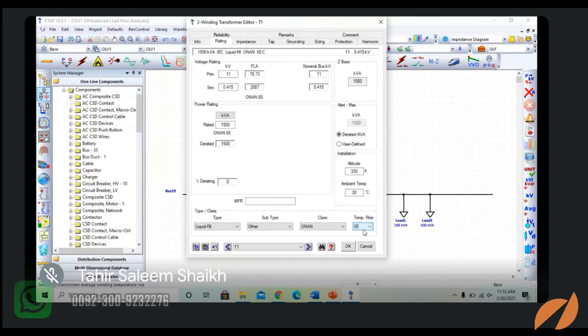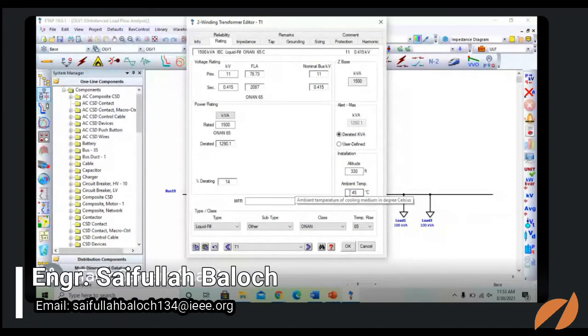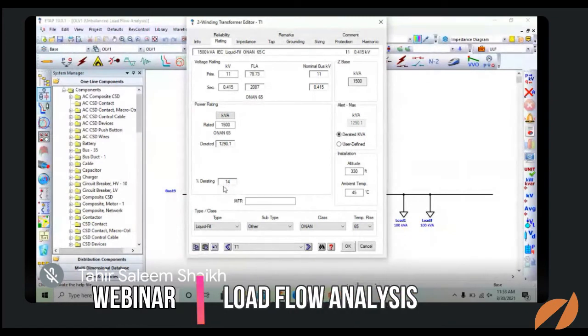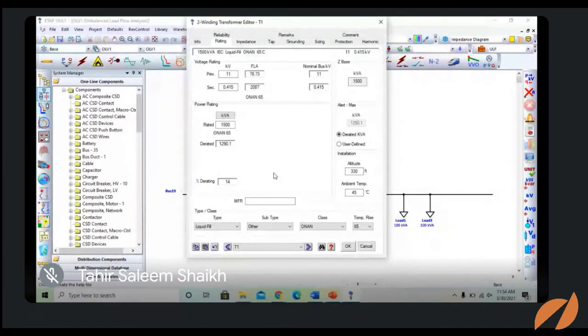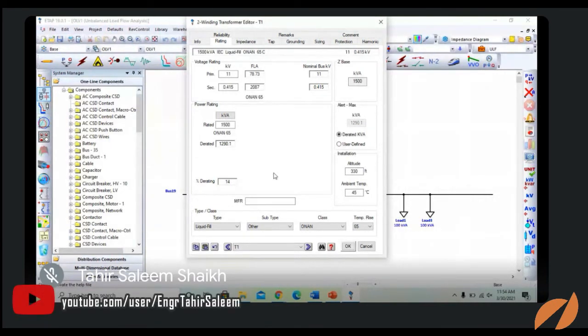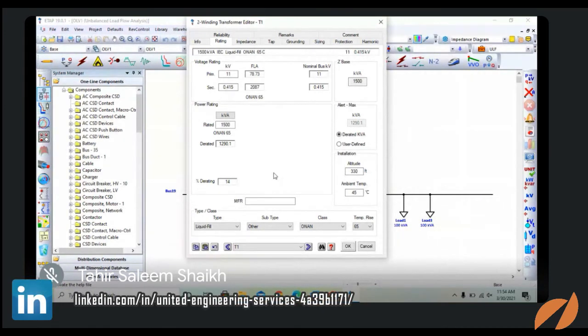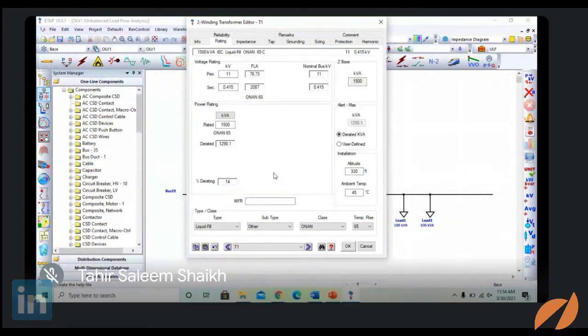Okay, temperature rise, we are selecting 65. For the ambient temperature, the environment which you are using, like in Karachi, we have 45 degrees. Depending on this ambient temperature, it has a derating itself. For example, at 30 degrees it was giving the complete 1500 kVA, and when I selected 45 degrees Celsius, it gave a derating of 14%, and it changes the transformer rating from 1500 kVA to 1290, that is about 1300. So this rating is affected because of the temperature rise.